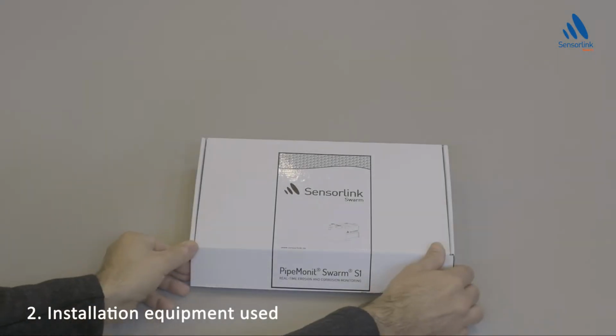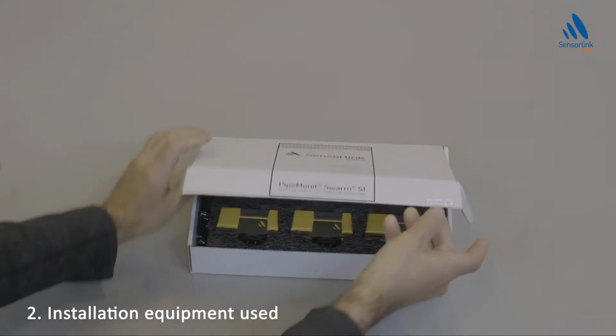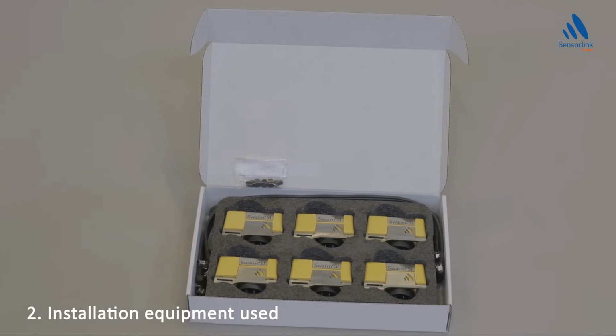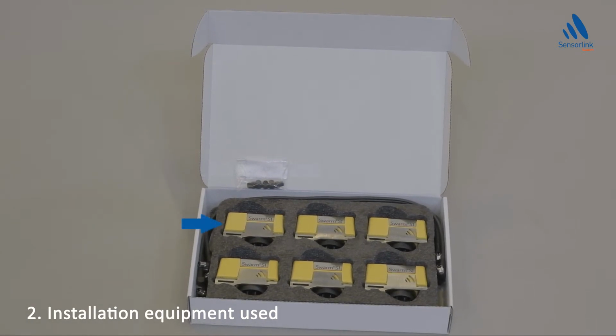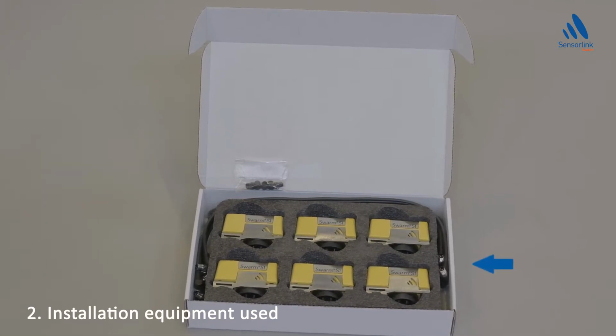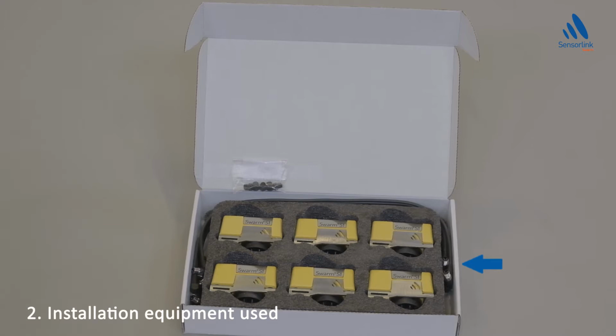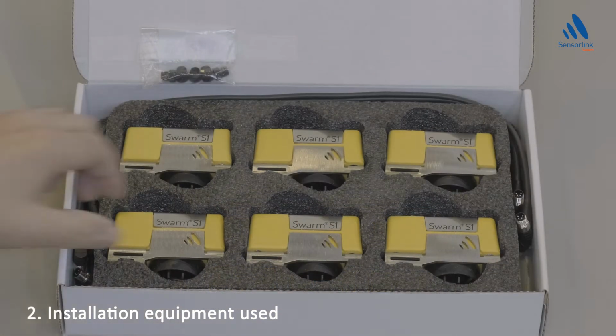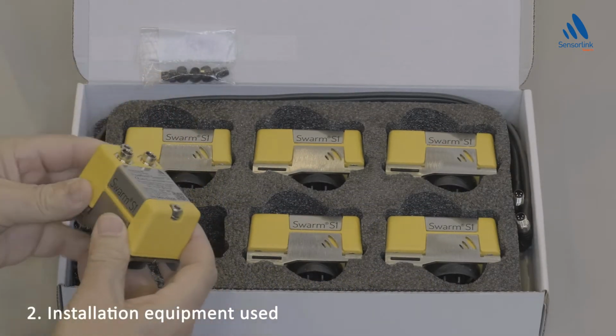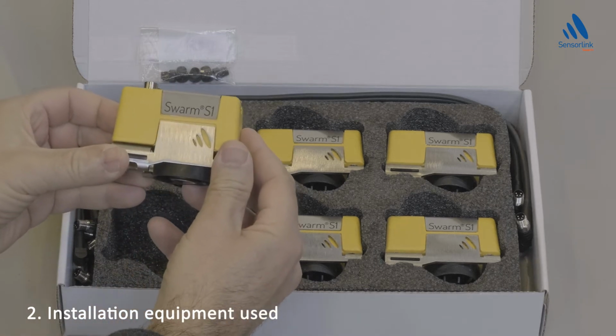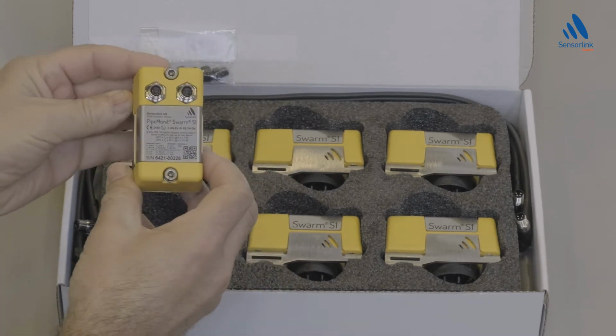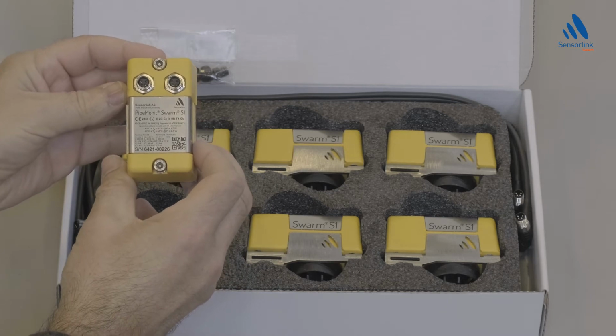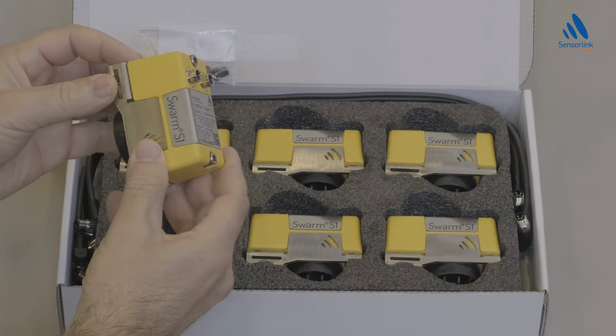The Swarm S1 sensors each come with a bracket, a 50 cm jumper cable, and blind plugs. This is the Swarm S1 sensor. This is the bracket. This is the 50 cm jumper cable, and these are the blind plugs. The jumper cable is used to connect from one Swarm S1 to the next in the chain. The Swarm S1 sensor can be mounted to monitor welds and will also work on homogeneous coatings up to 3 mm in thickness, like for example PP and epoxy.